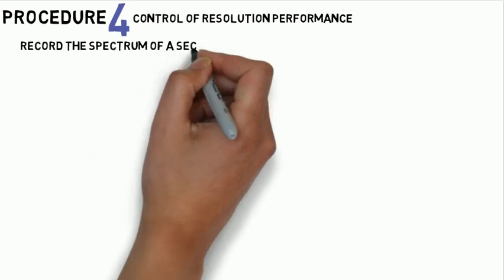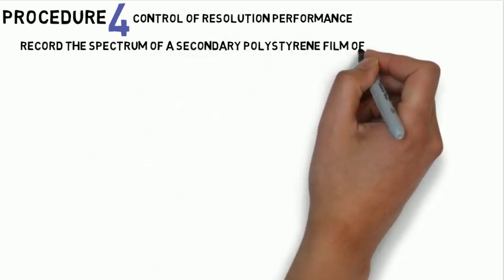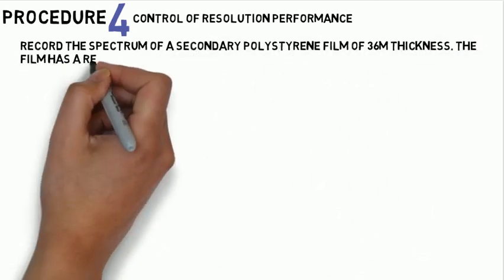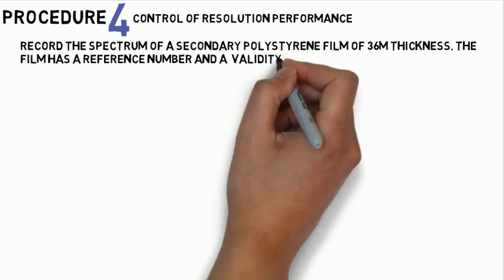Procedure 4 control of resolution performance. Step 1: Record the spectrum of a secondary polystyrene film of 36 micrometer thickness. The film has a reference number and a validity certificate traceable to NPL.